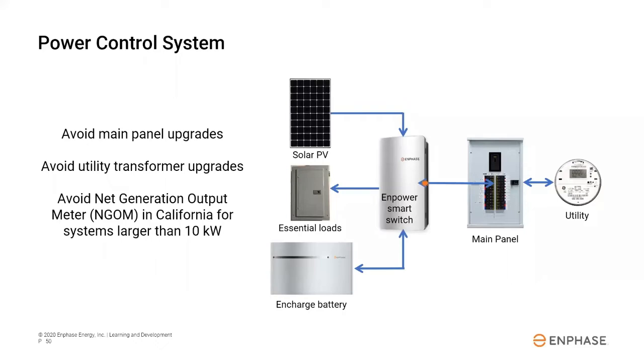Lastly, we have power control systems. So the advantage of power control system is that it helps avoid costly upgrades and additional hardware by controlling the amount of electrical current flowing to the main panel and the utility grid. Many AHJs approve the use of PCS, so I recommend checking with your local AHJ before you plan on using PCS.